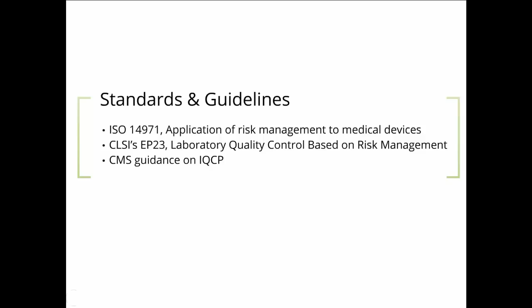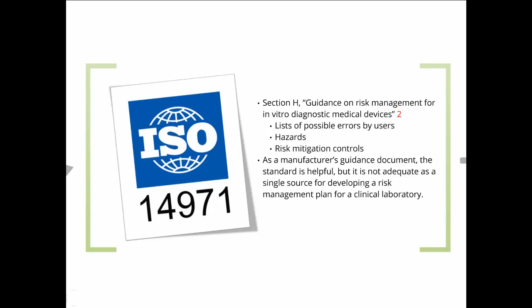ISO 14971 is intended for use by manufacturers developing medical devices, and while not intended for clinical decision-making, there is valuable information in Section H. Guidance on risk management for in vitro diagnostic medical devices. The guidance document provides valuable example lists of possible errors by users, hazards, and risk mitigation controls. As a manufacturer's guidance document, the standard is helpful, but it is not adequate as a single source for developing a risk management plan for a clinical laboratory. The document is sold on ISO standards websites.